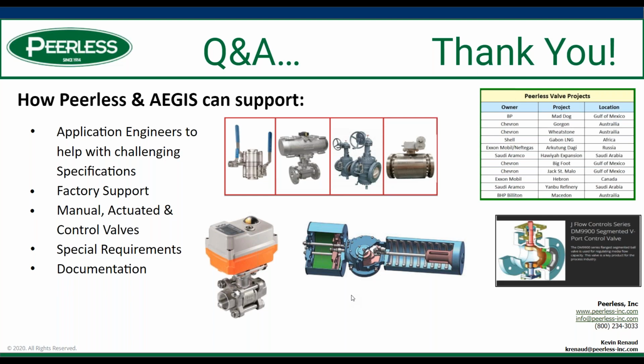We've looked at different actuators, but the footprint required for an actuator is only enough to close or open and control that valve. So sometimes a larger actuator is required, and sometimes a smaller actuator can be used. Cylinder actuators a lot of times can take the place of that, like Valtek or one of those kinds of companies, and we have those as well. Cylinder actuators are more compact and create a lot more thrust force, but typically they require a little bit more air to get the same job done.